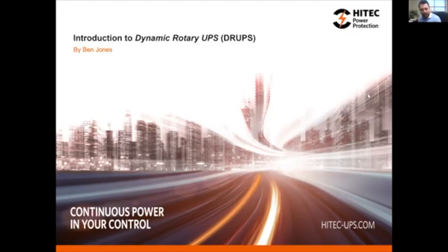It's about 8 minutes. The reason is the diesel engine—just to give nice round numbers—if you've got a 2 meg system, you've probably got a 2.2 meg alternator to allow for additional losses, and probably a 2.2 to 2.3 meg engine. We don't want to oversize the engine just to charge the flywheel quicker, because it doesn't provide value. We can do that if you specifically want the flywheel charged quicker, we can oversize the engine, but typically it's 8 minutes.